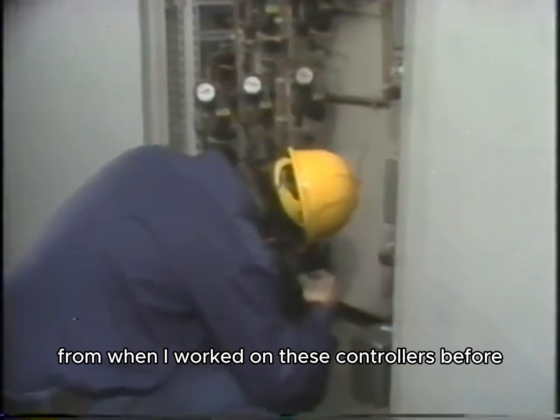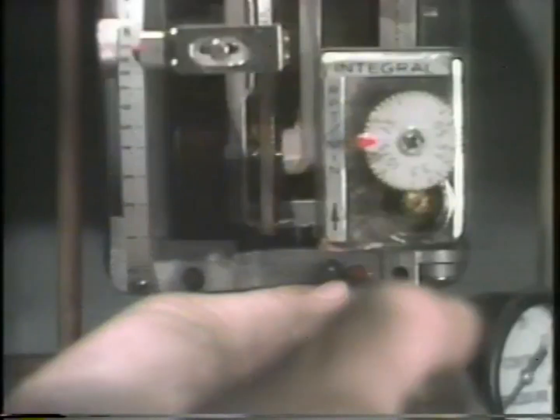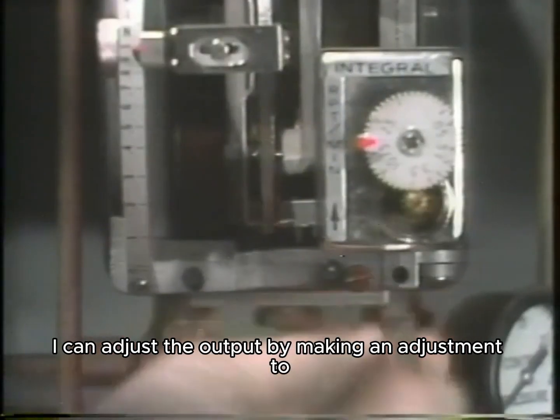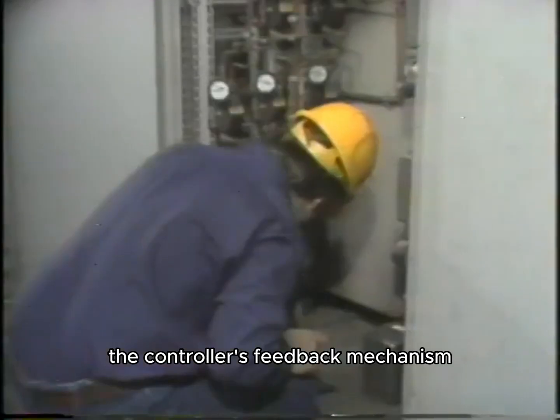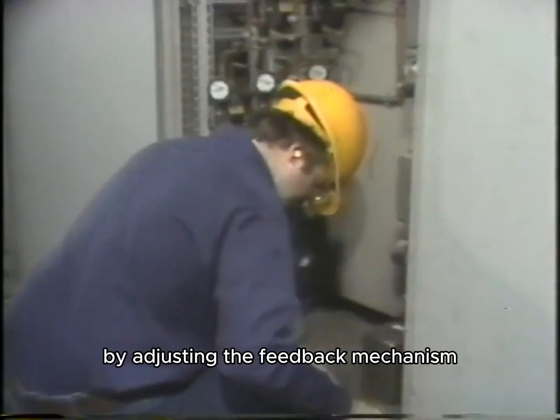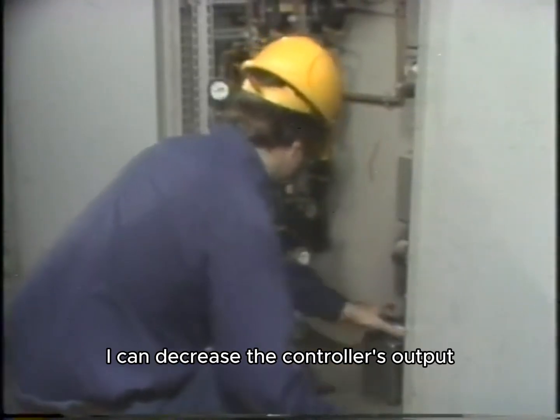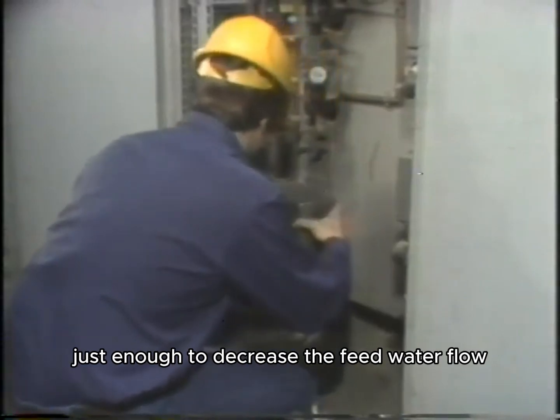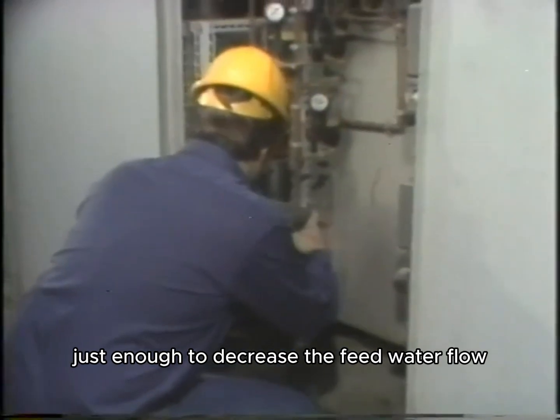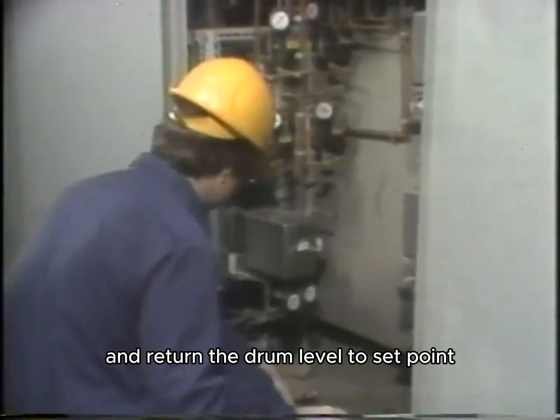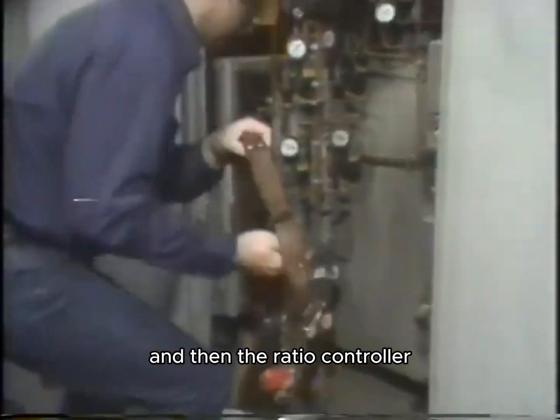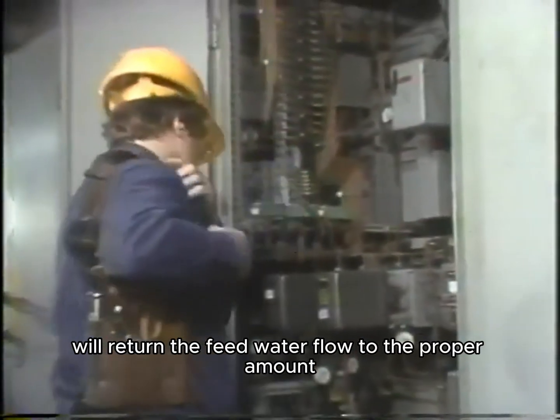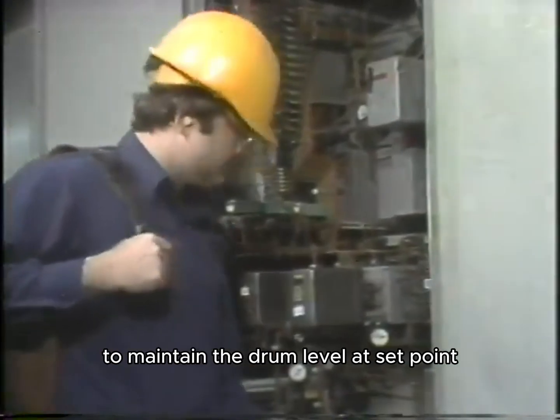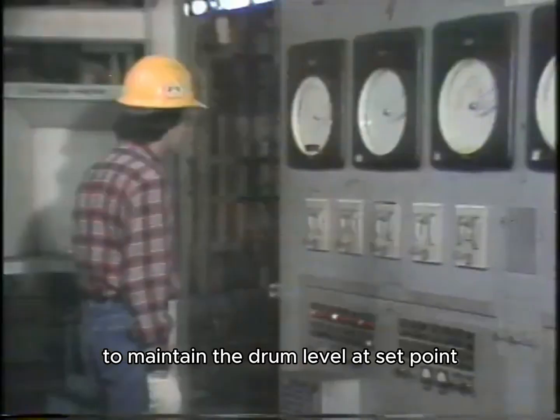I remember from when I worked on these controllers before, I can adjust the output by making an adjustment to the controller's feedback mechanism. By adjusting the feedback mechanism, I can decrease the controller's output just enough to decrease the feed water flow and return the drum level to set point. And then the ratio controller will return the feed water flow to the proper amount to maintain the drum level at set point.